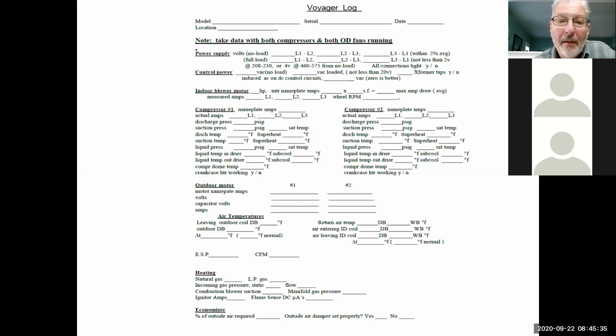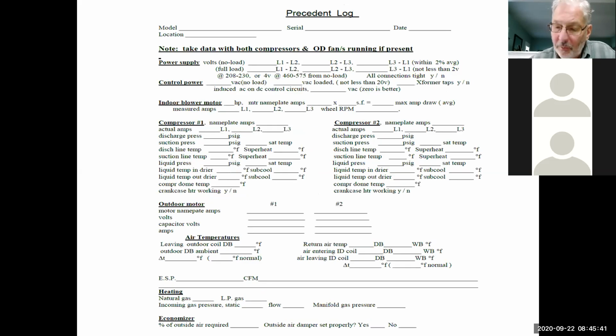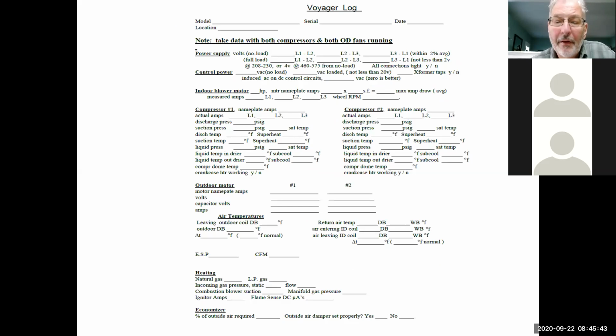Last thing is startup sheets. You guys are having problems in the field, do a startup sheet. We have Precedent logs, we have Voyager logs. If you need these, let me know. I can email them out to you. But by the time you get down through the voltage and the amperage and the subcool and superheats, usually you can tell what's going on with the system. But do a proper startup, and keep them in your file, and make your life a whole lot simpler.